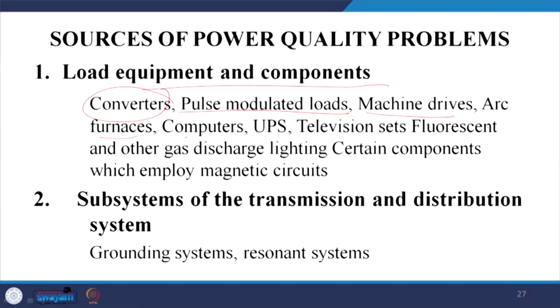Now, sources of the power quality problem: load equipment and components. These are, as I told you previously, converters, mostly DC to AC, pulse modulated loads, machine drives, arc furnaces, computers. Now, a standalone computer may consume a very small amount of power, but for example in our IIT Roorkee campus, we have 10,000 students. Once they go back, everyone turns on the computer, desktop or laptop. So that power becomes harmonic power, and it is not less.